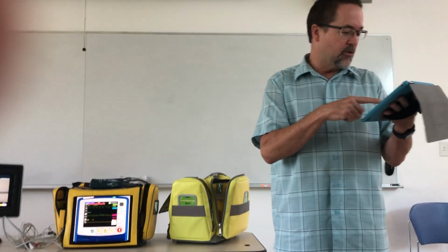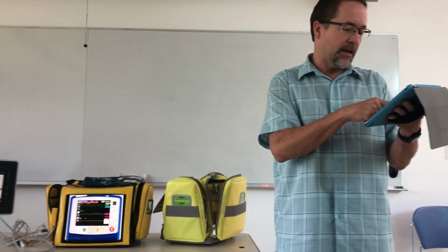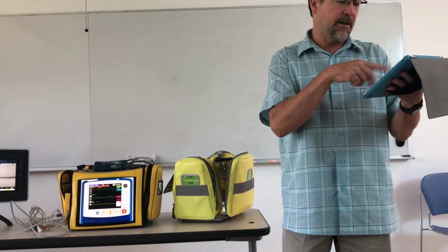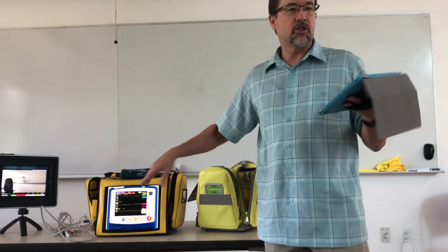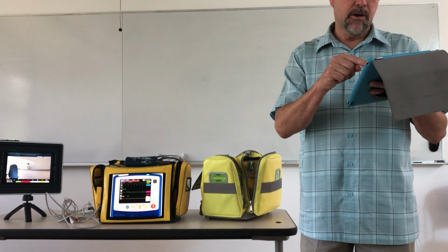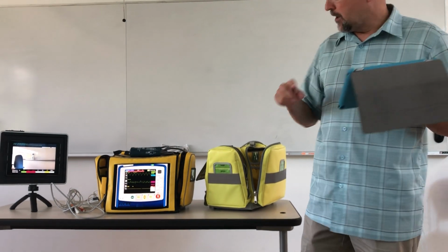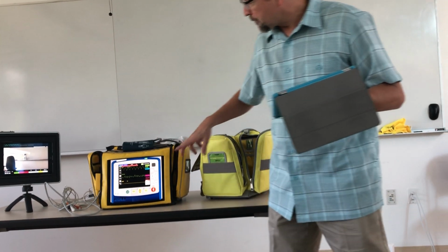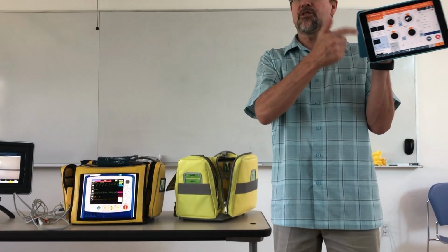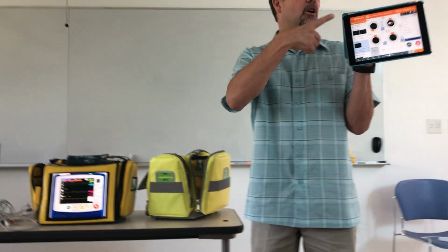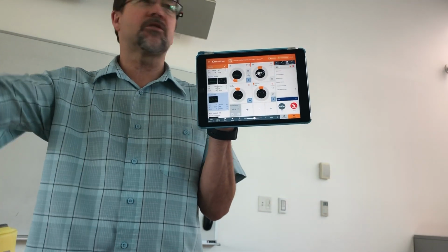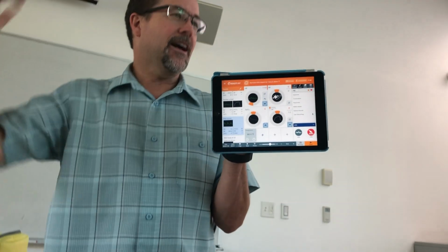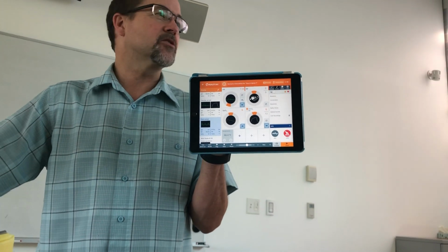The other thing you can do is you can change, and I don't think I did that on this particular one, I didn't have any end-tidal CO2 value, but you can program it in. Let me turn that off because it's annoying me. You can pre-program each of your events so that you have a cardiac arrest, and in the post-cardiac arrest, your end-tidal CO2 jumps to whatever you want it to be as another clue that they just got a spontaneous circulation back.